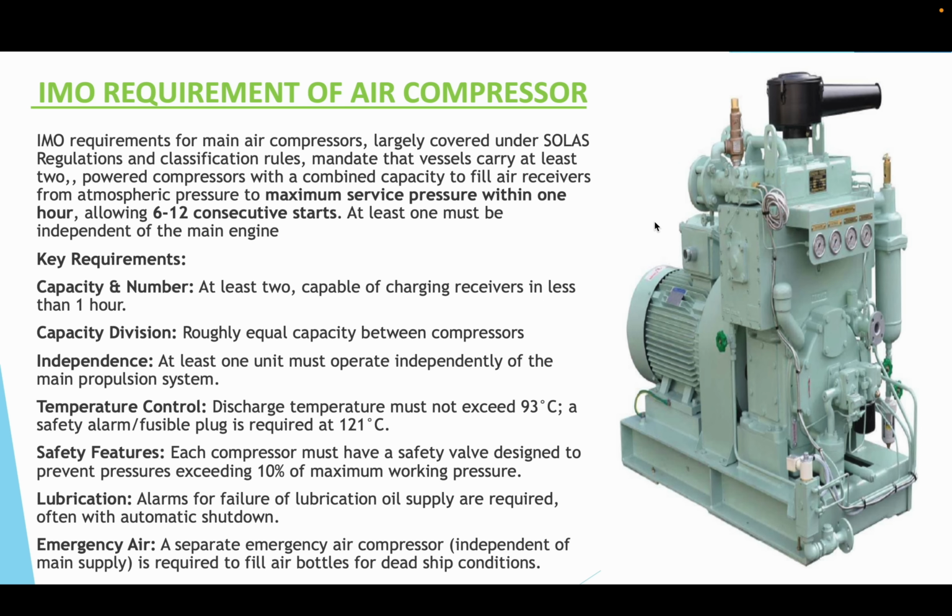So what does it mean? It means that the air compressor should be designed in such a way that it should be able to fill the air bottle within a period of one hour, and after that the compressor will be stopped, and the amount of air which is filled in the air bottle should be able to give 12 consecutive starts in case of a reversible engine and 6 consecutive starts for the non-reversible engine.